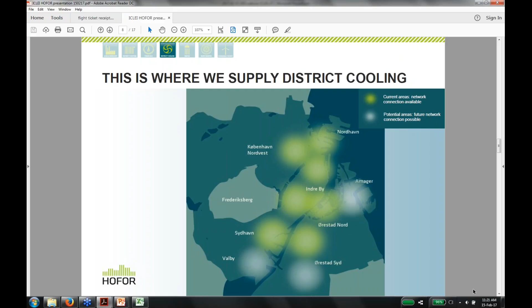Next slide, please. The production comes from three sources. One is seawater, taking water from the harbor and exchanging it with a seawater heat exchanger, delivering free cooling most of the year, maybe 9 months. At peak loads, we have our compressor units, up to 5-8 megawatts of capacity, running on ammonia. Again, we use seawater to cool the condenser part of the compressor, so we benefit from free cooling the whole year.